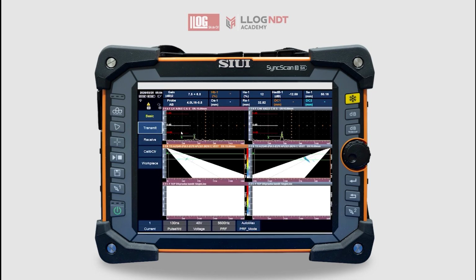Before starting, it is important to note that the required instrument standardizations have already been completed: sound velocity, wedge delay, sensitivity, and TCG curve generation based on the reference block in accordance with the applicable code. To begin scanning, go to the Scan option and adjust the range. The range should be set to display at least 2 legs of the ultrasonic beam, based on the thickness defined in the scan plan. For this example, set it to 50 millimeters.